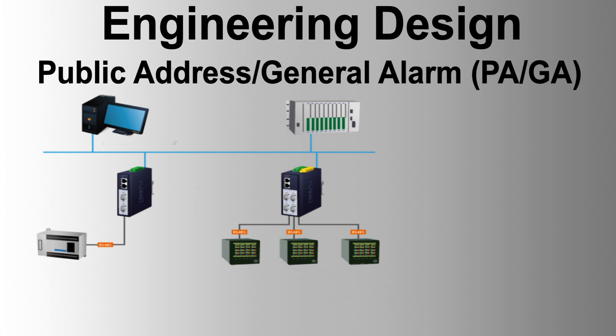PAGA external interfaces: the system incorporates a telephone interconnect paging panel connected to the local PBX system, enabling remote broadcasts from telephone extensions. An alarm and tone message generator interfaces with the fire and gas system. DTMF tones control recording and playback of messages. Plant radio sets with DTMF keypads access the PA system similarly to telephones.